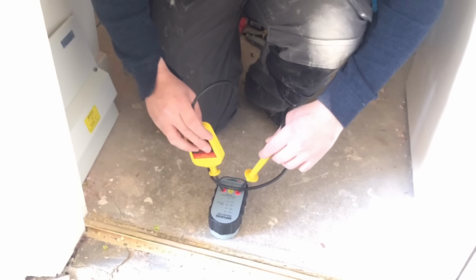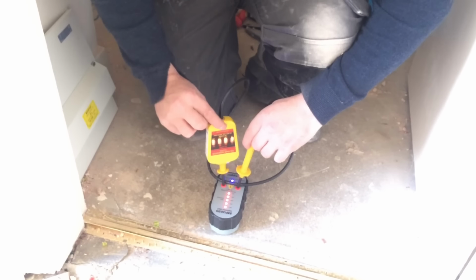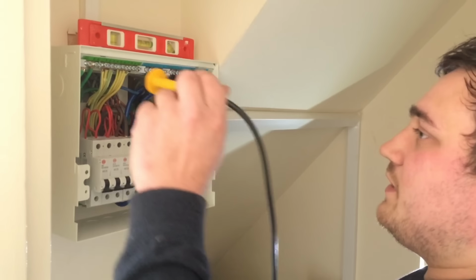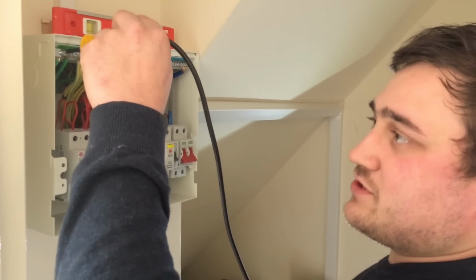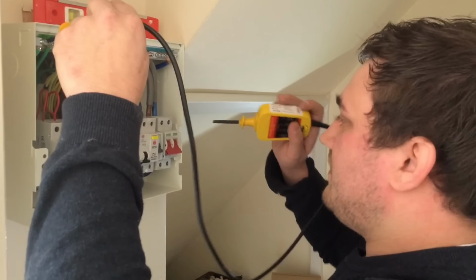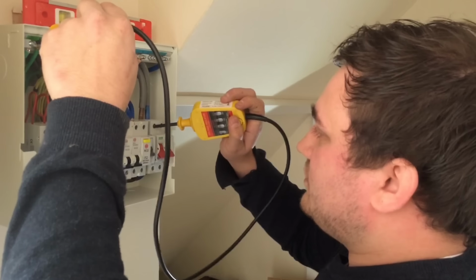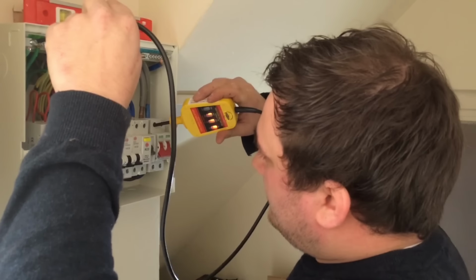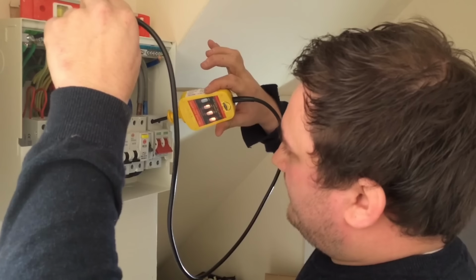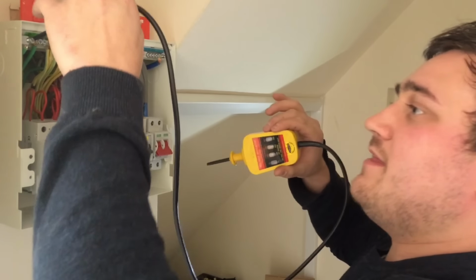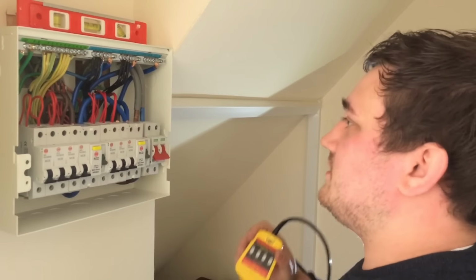We're now going to recheck the polarity of the supply. With that I'm going to use a voltage indicator and a proving unit. I'm just going to prove my voltage indicator is working, that's fine. Now we're going to check it. We're going to go on to the least dangerous conductor first, that being the earth bar in this instance, and then to the top of the main switch on the line conductor. When we have voltage, we're going to come off the most dangerous, then off the least dangerous.